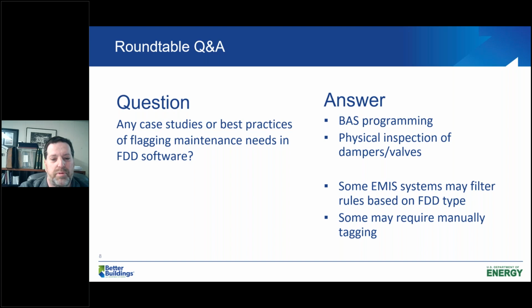I've seen one provider, on the same campus, depending who programmed it, would either use the abbreviation of the building or the full name of the building. So you want to try to be really consistent with the tagging of the equipment. And then the equipment in the work order system, you want that to be consistent as well. The EMIS system will also require the same consistency because you're all talking the same language. So the best practice for flagging maintenance is making sure you're talking the same language.